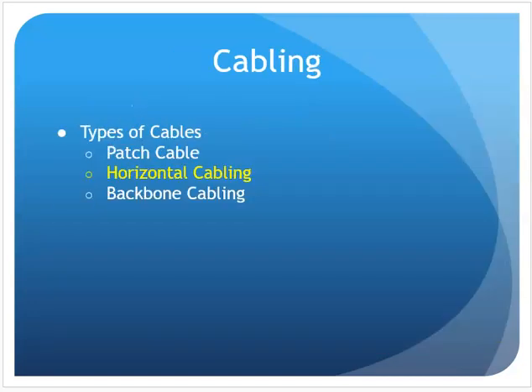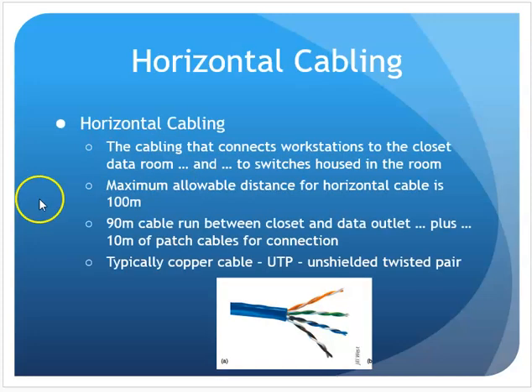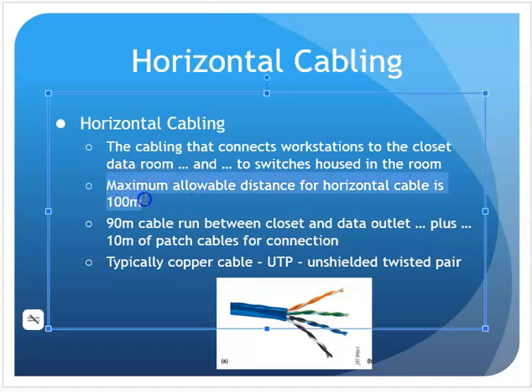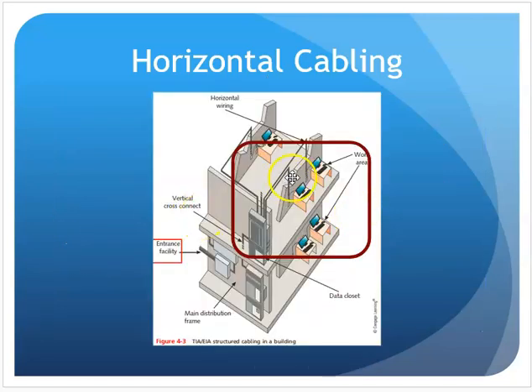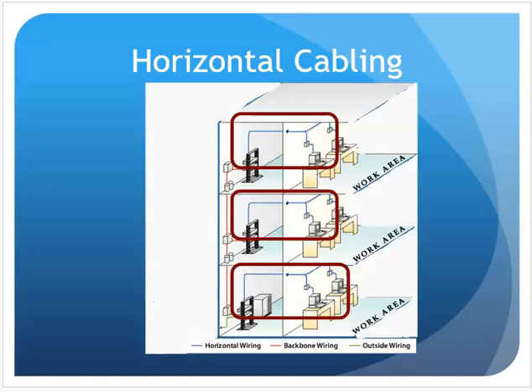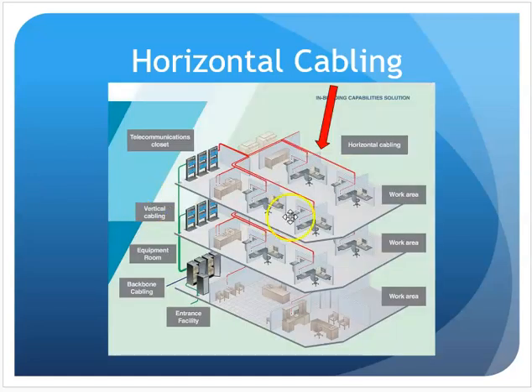The next type of cabling we run into is the horizontal cabling. The horizontal cabling is going to go from that work area into the data closet, into the patch panel. The maximum allowable distance for our twisted pair cabling is 100 meters. So what they usually denote is 90 meters should be the max for this horizontal cabling. 90 meters for the horizontal cabling between the outlet box and the patch panel in the closet. So this part of the cable run from the outlet into the closet. That is your horizontal cabling.